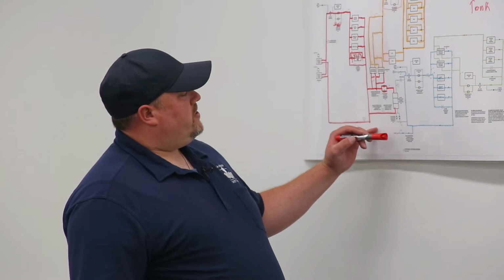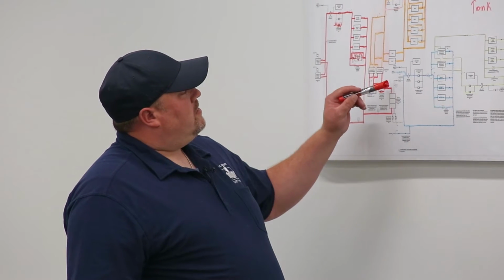Okay. On the campus chilled water loop, there's a control valve on the return as it would leave. The supply side of the chilled water loop from campus is to maintain always to be open. There is an expansion tank in the system that in the event that you would have to drain these central utilities, you could close off the valves located inside the building and we have our own system makeup water, and the expansion tank that would normally be closed could be opened, and this chilled water loop with the chiller would maintain itself for the building.